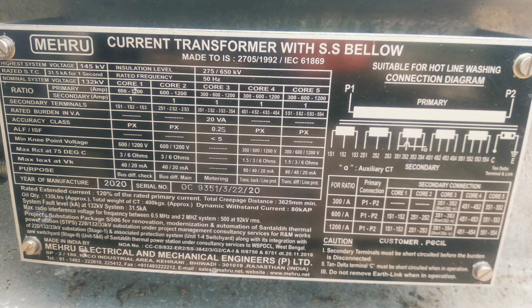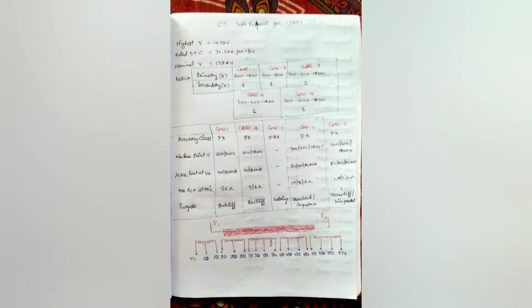So right now, as I said, this CT comprises 5 cores: core 1, core 2, core 3, core 4 and core 5. Core 1 and core 2 have taps 1S1, 1S2, 1S3, which means 1S1 and 1S2 having a core of 600 amps and 1S1, 1S3 having a core of 1200 amps. In this CT, the secondary amps is 1, which means for all the cores, the secondary ratio is 1.